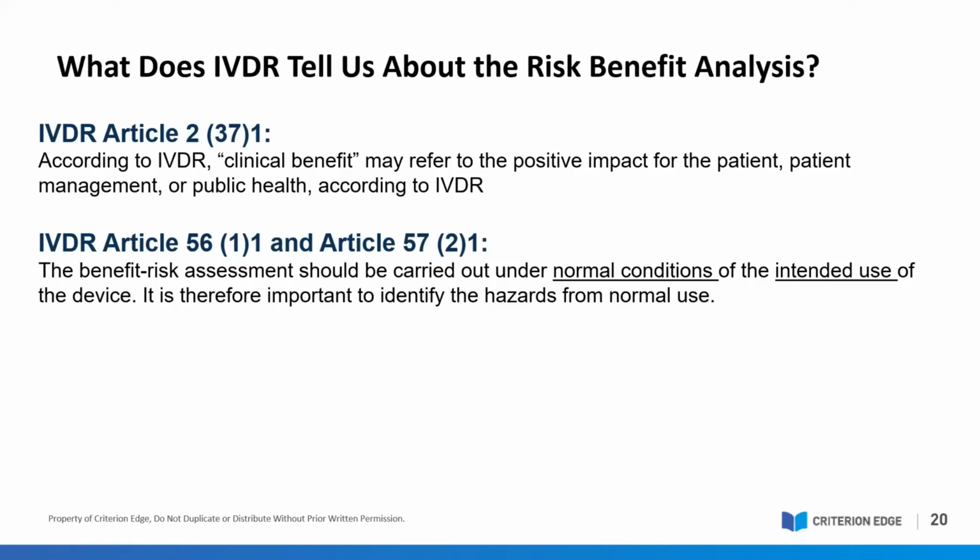This can come into play if you have a test that is not necessarily the most scientifically advanced, highly accurate test on the market, but it can be conducted in home or in the field compared to a laboratory type of test. The benefit risk analysis should be a description comparing exactly when and where and under what circumstances your device can be considered state of the art. And so that's where you will pull all these sections together into this final analysis.